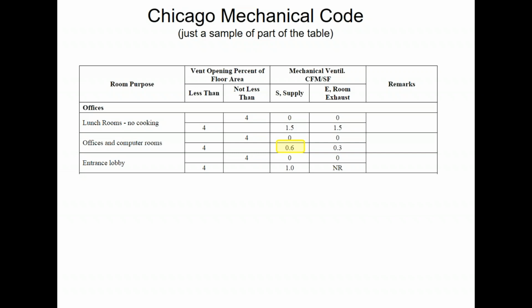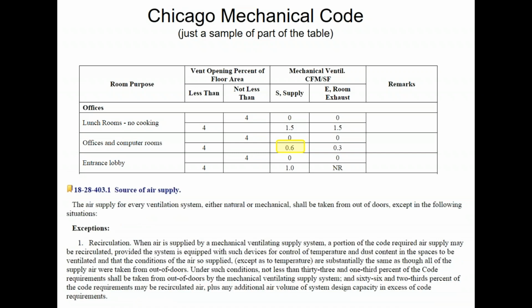In this case, 0.6 CFM per square foot for an office. Then they tell you additionally that 1/3 of that needs to come from outside. Right? So in this case, 0.2 CFM per square foot from the outdoor. Very complicated way to do it. If you do work in the city of Chicago, it seems normal to you because you've been doing it for 100 years and it's fine. But if you're from outside, you're like, what?